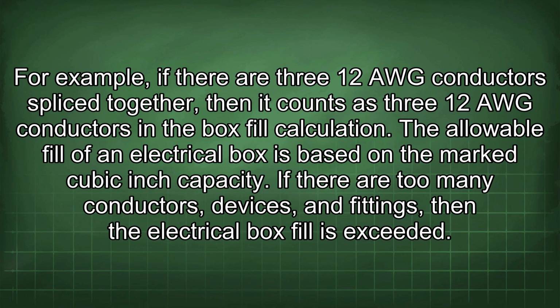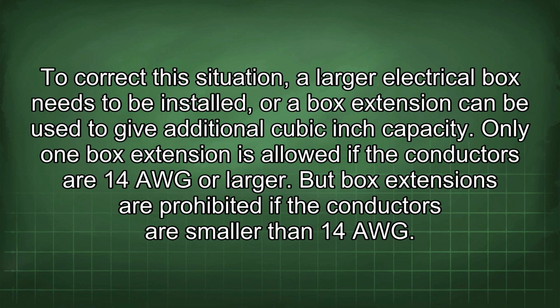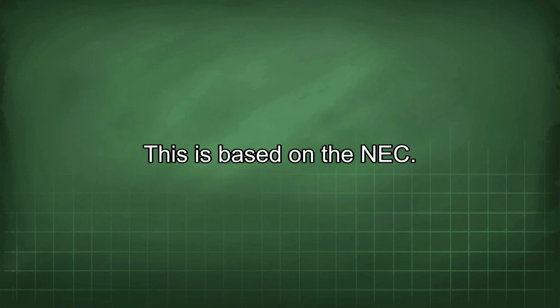If there are too many conductors, devices, and fittings, then the electrical box fill is exceeded. To correct this situation, a larger electrical box needs to be installed, or a box extension can be used to give additional cubic inch capacity. Only one box extension is allowed if the conductors are 14 AWG or larger. But box extensions are prohibited if the conductors are smaller than 14 AWG. This is based on the NEC.